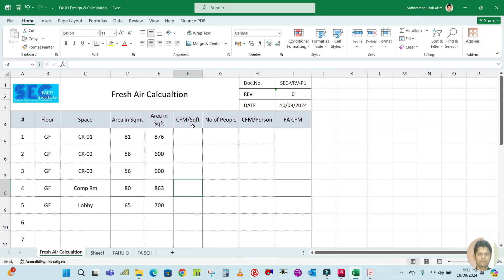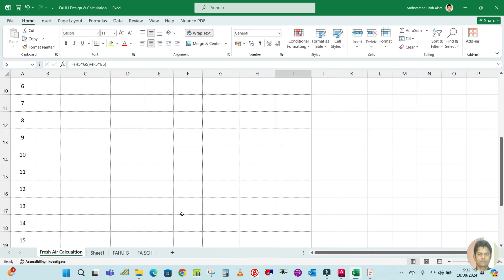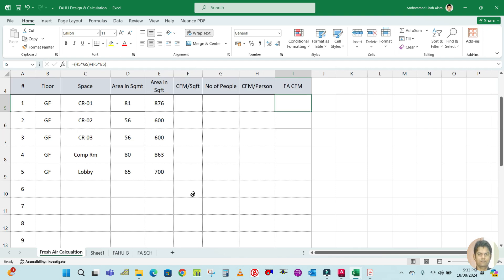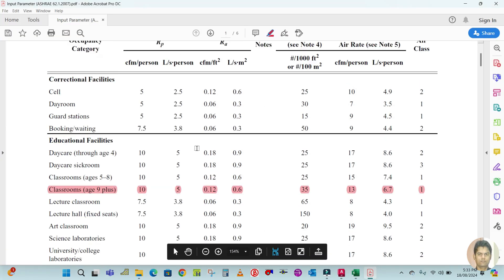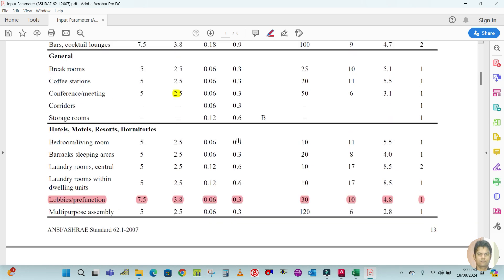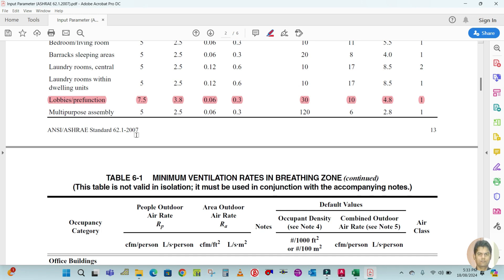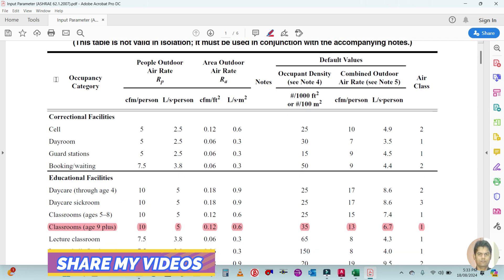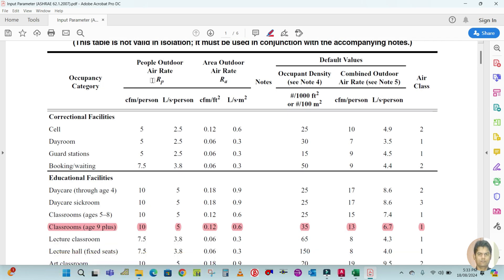Next we need CFM per square feet, number of people, and CFM per person. The formula for fresh air calculation is: CFM per person × number of people + CFM per square feet × area in square feet. We use ASHRAE standard 62.1-2007, Table 6.1, which gives the minimum ventilation rate in the breathing zone by occupancy category, listing people outdoor air rate and area outdoor air rate.